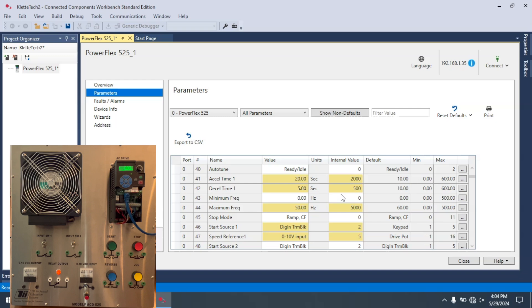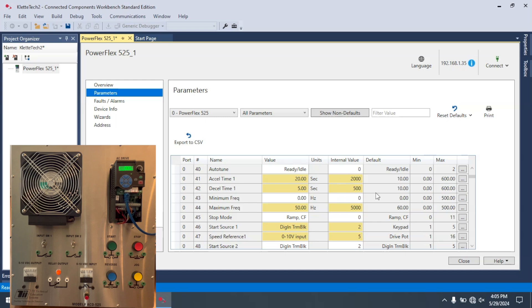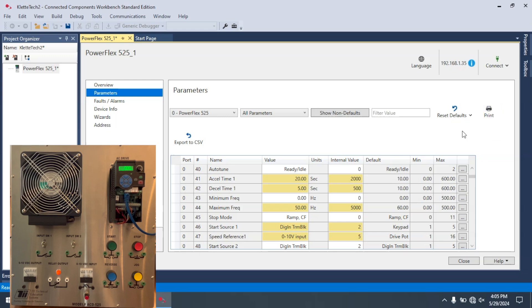Now let's say you originally put all the parameters into the 525 through CCW. But then over the couple of years, you've gone through and manually changed some things on the VFD. Before you pull that VFD out to be swapped out or sent in for repair, you're going to want to upload all that information so that you can store it. You can also come here and actually print all of this out so you have a paper copy of it.